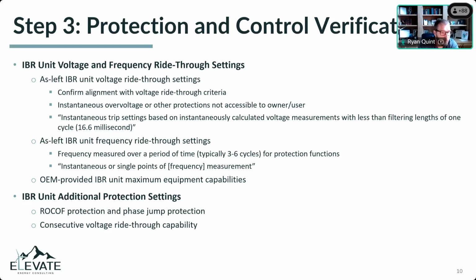And we've got frequency ride-through on the units, right? There's a measurement window. There's the curves themselves. There's a don't-use-instantaneous-or-single-points-of-frequency-measurement clause. All these clauses or items in the standard we have to make sure we've addressed. And often what we're seeking is, what's the max capability of the specific turbine or inverter we're working with? Because we'll likely need that, especially if that existing site doesn't comply with the standard. The next logical step is, how far can we push it out? Well, we need to know what the capability is to know how far we can push it out. So we need to know those things.